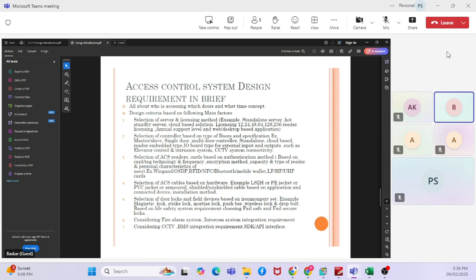Apart from that, an IO board is needed for inputs and outputs, if you want to connect external inputs like lifts, to monitor lift status and lift control at every floor, or to connect with an intrusion system or CCTV system. So we need the IO board for that. This is how the selection of the controller happens.